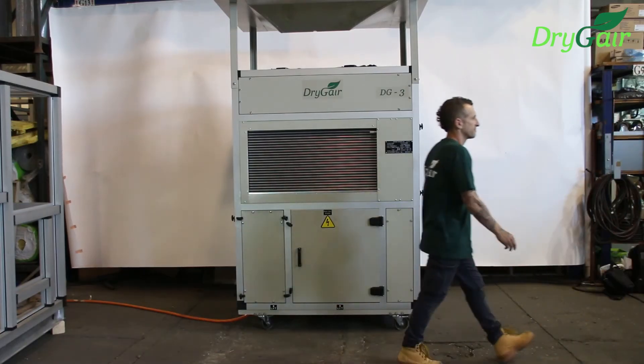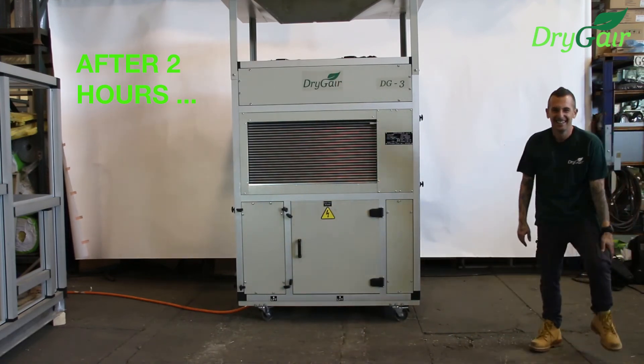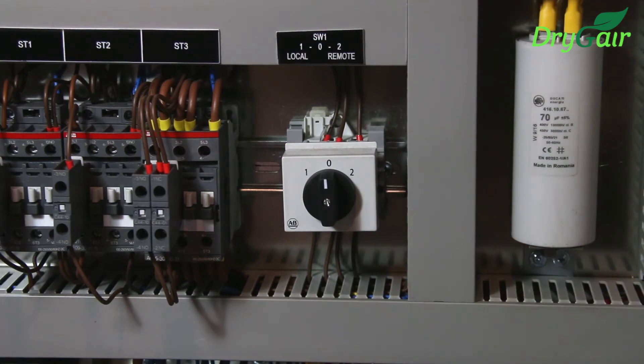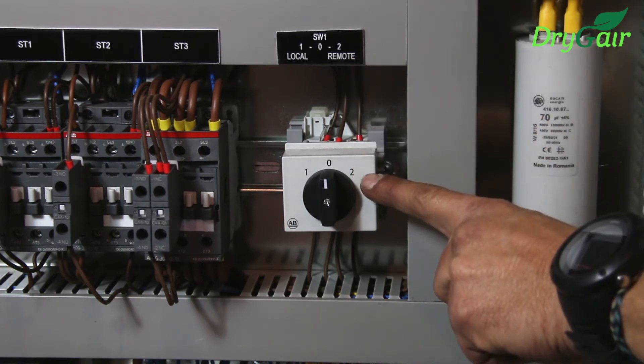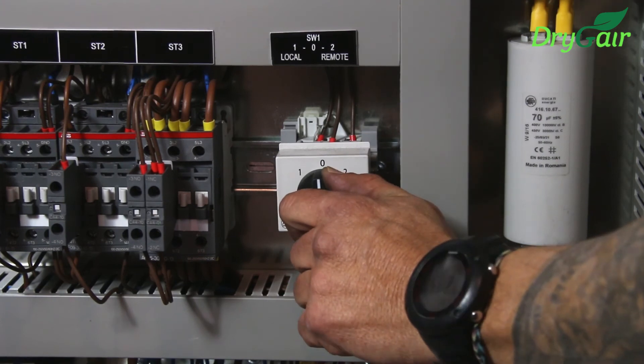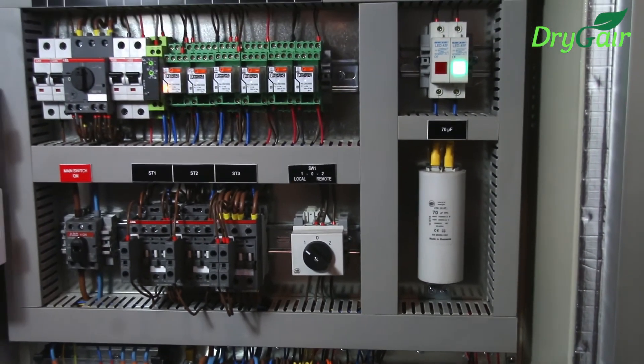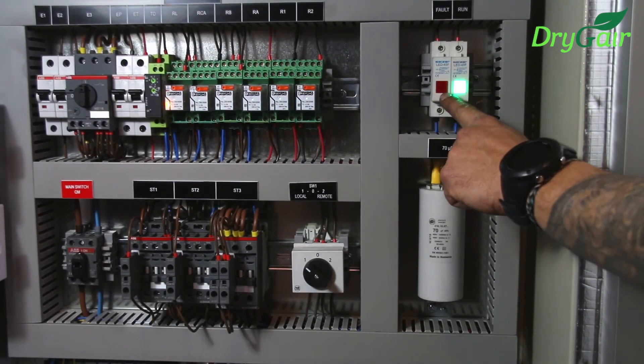Remember that when you first install the DryGair unit, you must wait two hours before you can begin to operate. Two hours have passed and now we are ready to begin. It has three operating modes. When set to zero, the unit is in disconnected mode and is off. When set to one, the unit is in local mode and operates according to the values set in the temperature and humidity controllers. When the unit is set to two, it's in remote mode and is operated and controlled by the climate control system. We will now turn the unit on to local mode. Toggling the switch will cause the green run light to turn on. Make sure that the red fault light isn't turned on. If it is, check the operation manual for troubleshooting.